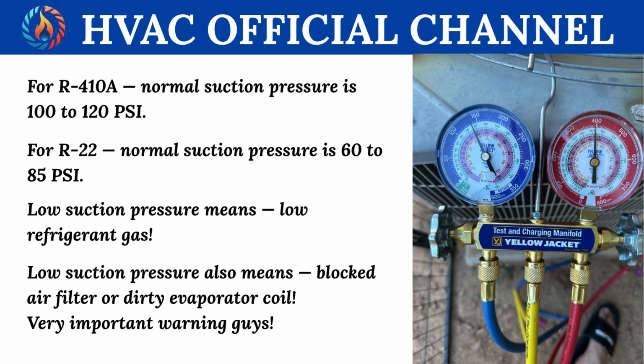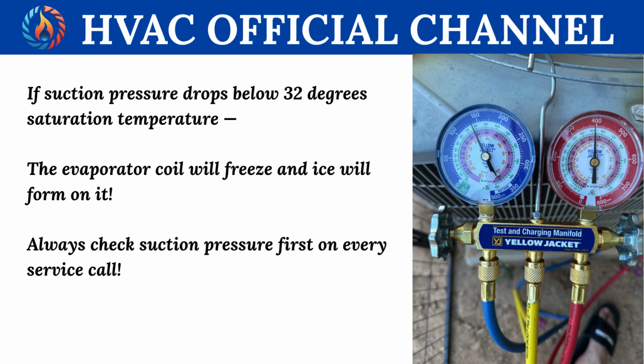Low suction pressure means low refrigerant gas. Low suction pressure also means blocked air filter or dirty evaporator coil. Very important warning, guys. If suction pressure drops below 32 degrees saturation temperature, the evaporator coil will freeze and ice will form on it. Always check suction pressure first on every service call.